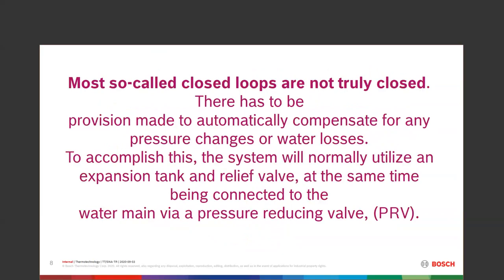Most loops are not truly closed. We have provisions for automatically compensating for pressure changes — as we heat water it expands, as it cools it contracts, so we might add a little more. We have an expansion tank, a relief valve, and usually a pressure-reducing valve connecting us to a water main. Some public water systems are fantastic with great water, but they all have dissolved oxygen. That dissolved oxygen and correct pH are the most important parts of treating our water.